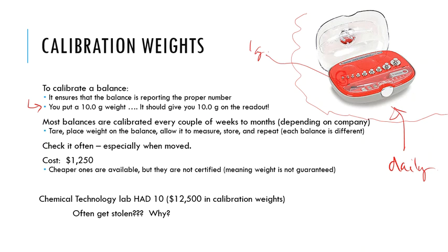So what that would mean is that in the very early morning, before anyone uses the balance at all, someone would take a calibration weight set and they would pick out one of the calibration weights that the procedure tells them to do, and they will put it onto the balance just to double check that it's reading the same today as it was yesterday.